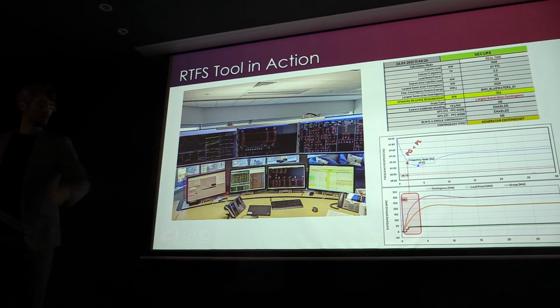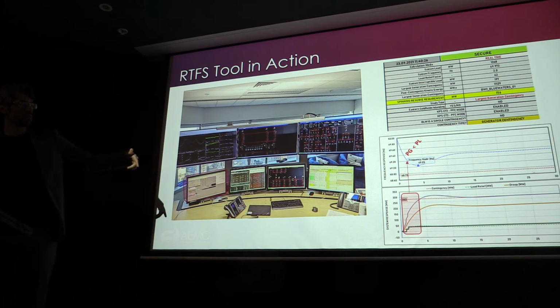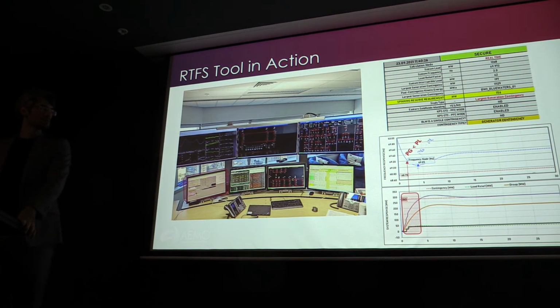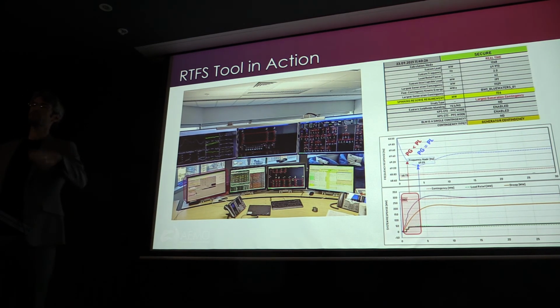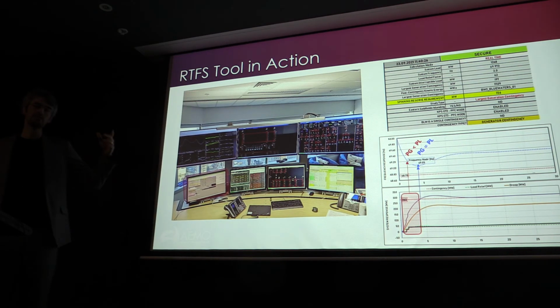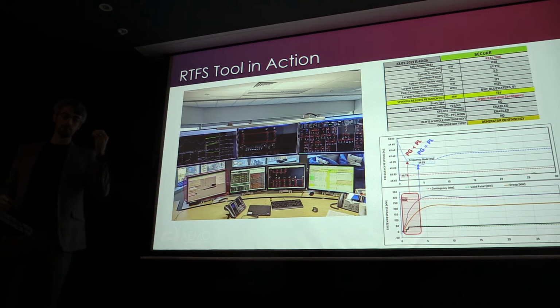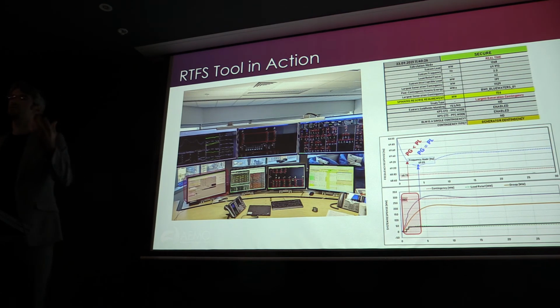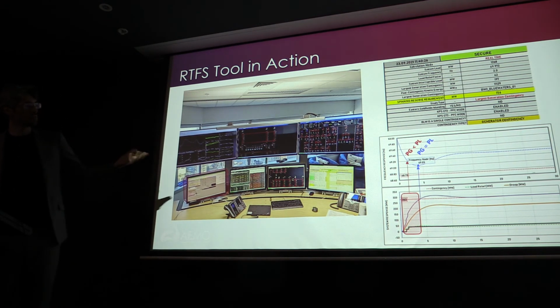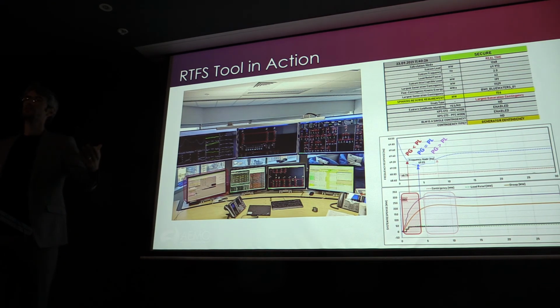In here, we had a contingency, so generation was less than load. Frequency was dropping, and we had frequency responses ramping up. By the time the response reaches the amount we've lost, you see the frequency nadir. That point means generation is equal to load, so you see RoCoF is 0, the rate of change of frequency, because frequency is an indicator of whether there is a balance between generation and load. Then the response, in terms of quantity, is higher than the megawatts you've lost, so frequency starts to recover because generation is now higher than load. At the end, you provide what you've lost, and you reach a quasi-steady state point.